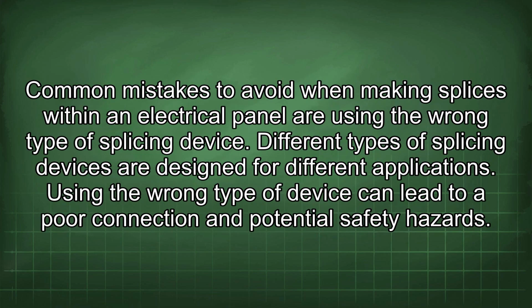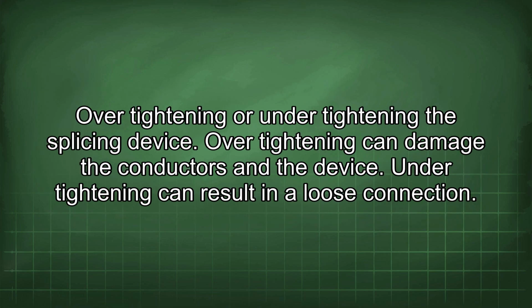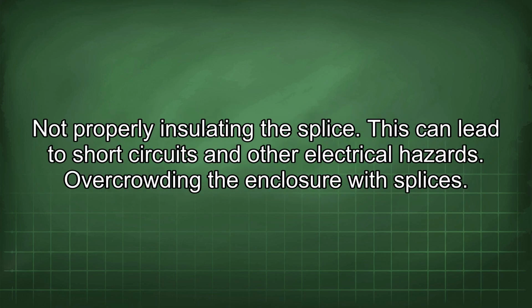Common mistakes to avoid when making splices within an electrical panel are using the wrong type of splicing device. Different types of splicing devices are designed for different applications. Using the wrong type of device can lead to a poor connection and potential safety hazards. Over-tightening or under-tightening the splicing device. Over-tightening can damage the conductors and the device. Under-tightening can result in a loose connection. Not properly insulating the splice. This can lead to short circuits and other electrical hazards.